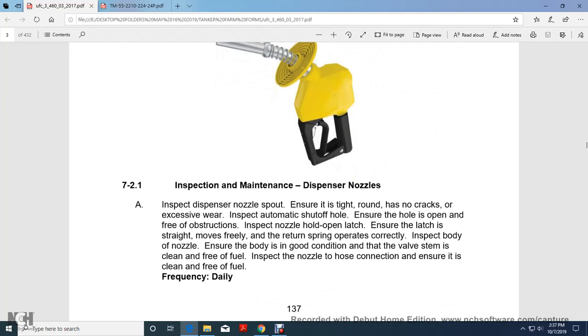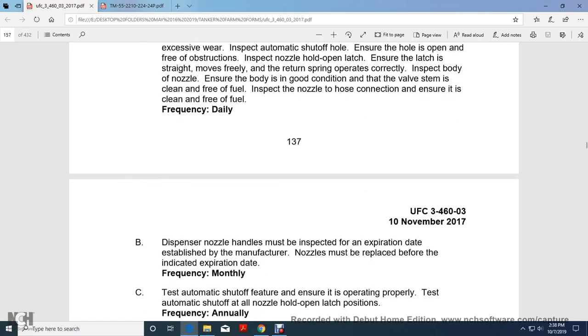Inspection and maintenance. Inspect the dispenser nozzle spout, ensure that it is tight and round and has no cracks or excessive wear. Inspect the automatic shut-off hole, ensure the hole is open and free of obstructions. Inspect the nozzle hold-open latch, ensure the latch is straight, moves freely, returns to its spring position, and operates correctly. Inspect the body of the nozzle, ensure the body is in good condition and the valve stem is clean and free of fuel. Inspect the nozzle to hose connection, ensure it is clean and free of fuel daily.